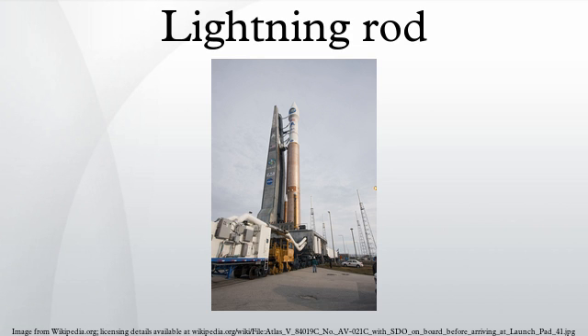Grounding systems without low resistivity to the ground can still be effective in protecting a structure from lightning damage. When ground soil has poor conductivity, is very shallow, or non-existent, a grounding system can be augmented by adding ground rods, counterpoise conductor, cable radials projecting away from the building, or a concrete building's reinforcing bars can be used for a ground conductor. These additions, while still not reducing the resistance of the system in some instances, will allow the dispersion of the lightning into the earth without damage to the structure.